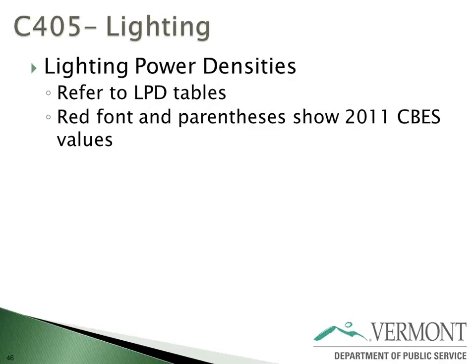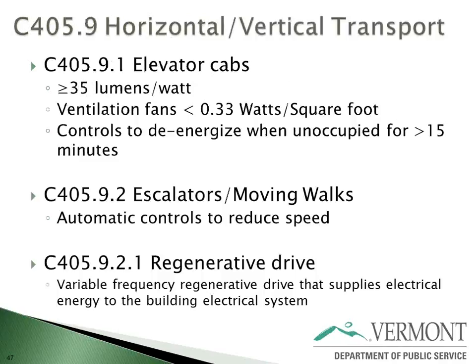For example, warehouses was at 0.6 watts per square foot, and is now proposed to be 0.66 watts per square foot. So who knows? People are just teasing out things, dialing it down, dialing it up. Office is another big one that's common, and it was 0.9 in our current code. It's 0.82 now. So they're really looking into the hundredths of decimal places to get these efficiencies squeaked out. And that's really it for lighting. It's mostly the power densities and the controls that are big.